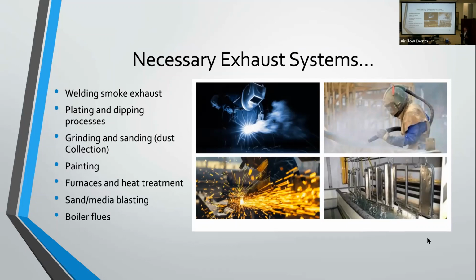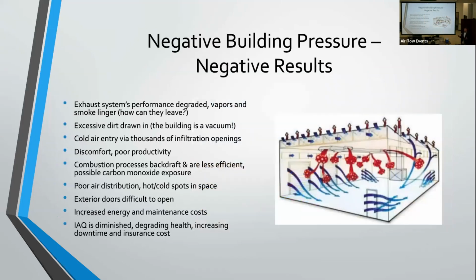Without the proper makeup air applied to these systems, you're creating negative pressure in that space. If you don't have the proper makeup air to account for that negative pressure, you can have a lot of problems. For starters, the exhaust system that someone paid a lot of money for can't function as efficiently as it should, because you're essentially starving it of the air it needs to do its job. Think of, like you'll see in a minute, trying to pull smoke out of a sealed container. You can't pull the smoke out unless you poke holes in the side of the box.